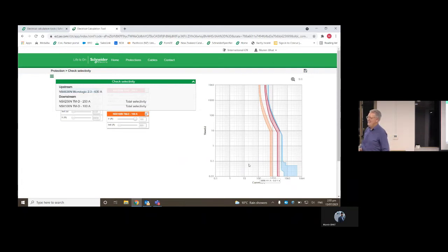In terms of the short circuit, where you're in the LI portion of the curve, let's say, for instance, that graph, the fault level is, let's say, 5,000. So you have your discrimination tables. When there's a fault, obviously all of them would want to operate at the same time.